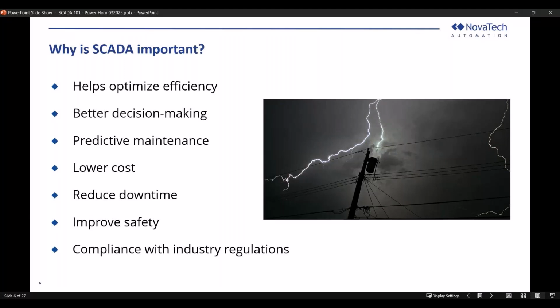A modern day SCADA system can not only analyze a large amount of data, it can store years and years of it, which helps with predictive maintenance. For example, you can graph the data to see trends—if five years ago a transformer blew up, was there data leading up to that situation? Now you can monitor for that kind of trend and perform maintenance on a transformer, or replace it, ensuring it's safe and operating properly, and lowering operation costs so you're not replacing a blown up transformer.